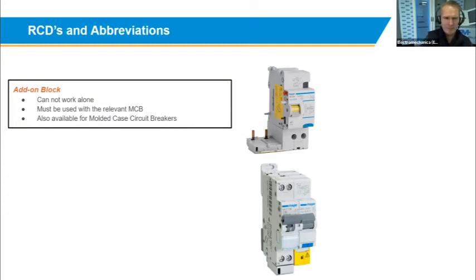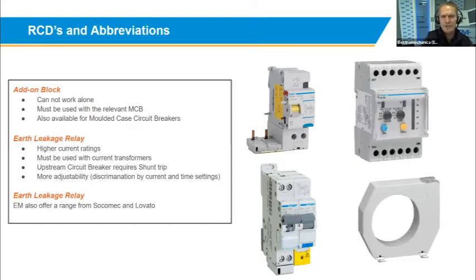Then what other types of earth leakage do we get? You also get what they call an earth leakage relay. So this is this unit here. It's a DIN rail module that plugs into a DIN rail, and it's used in higher rated circuits. So for example, you've got a 400 amp circuit breaker and you want to add earth leakage protection to that. Although in the moulded case circuit breaker, you also have the option to add an add-on block, but you can also go for an earth leakage relay like that one. But with that, keeping in mind, you need to add a toroid, a CT, to pick up the imbalance. And then inside your circuit breaker, you need to add in a shunt trip, because again, there's no current going straight through this unit.